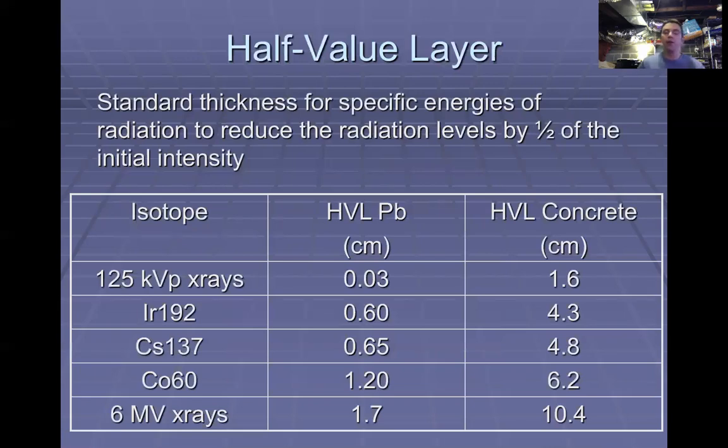I mentioned half value there and how it's similar to a half-life. It's sort of the half-life for shielding. What it represents is the amount of material it takes to take a certain intensity radiation beam and reduce it to half that intensity. That's really what it means.